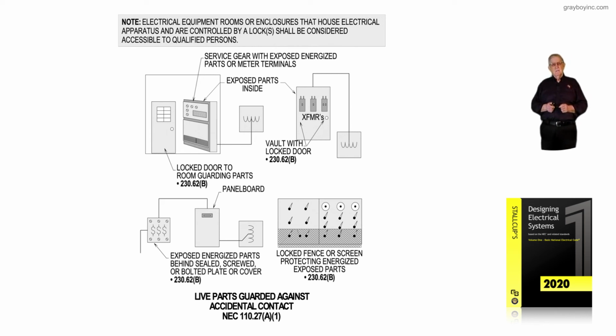Now, this illustration and this figure is illustrating that live parts at 50 volts or more have to be guarded from accidental contact from employees, passersby, and people that are in and around this equipment with their work job procedures that have been assigned to them by the facility. And then the people that actually work on this equipment now have to be qualified to have the access to this equipment in accordance with this rule, as well as NFPA 70E.